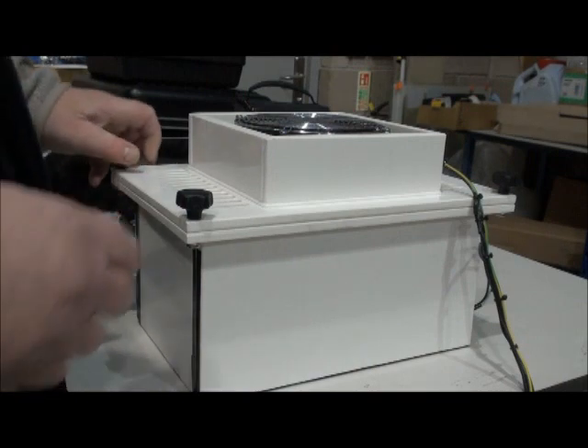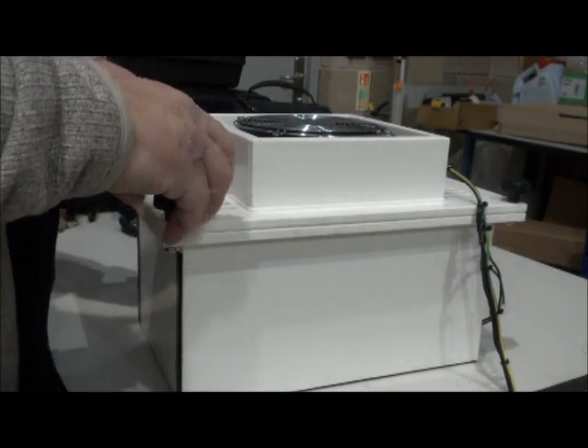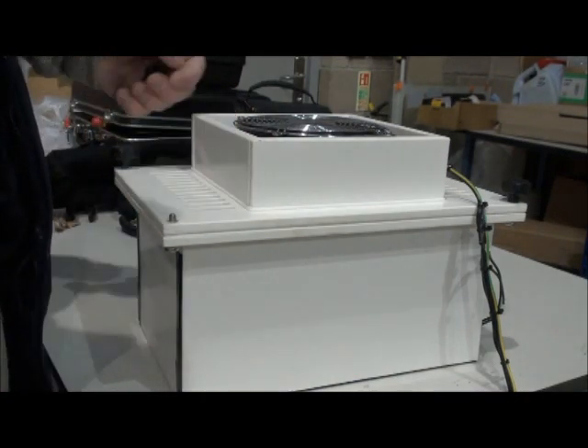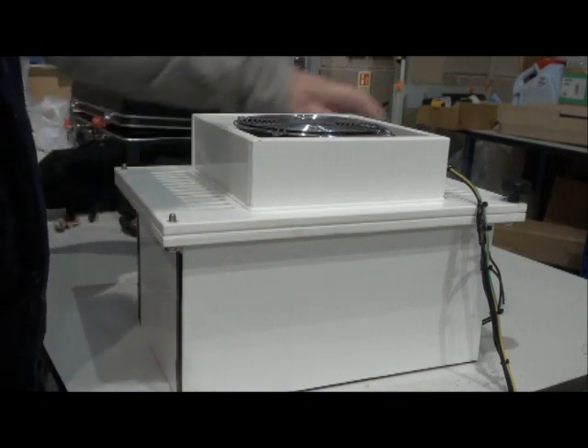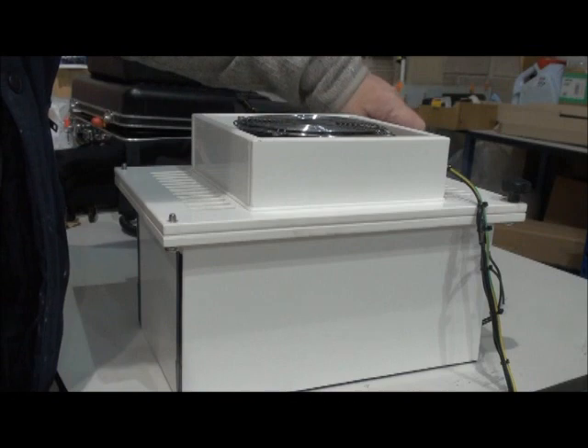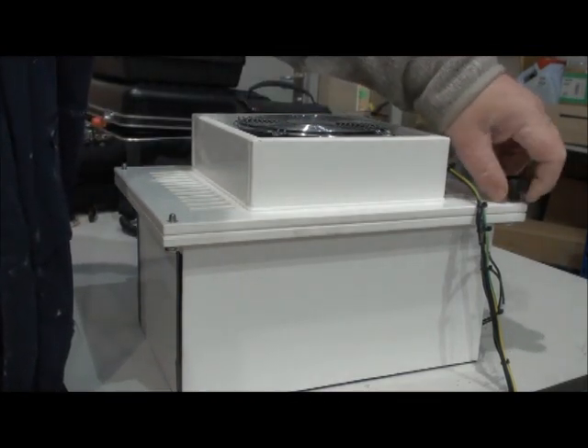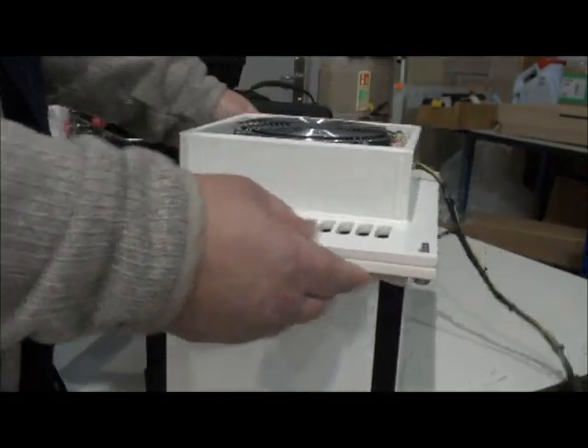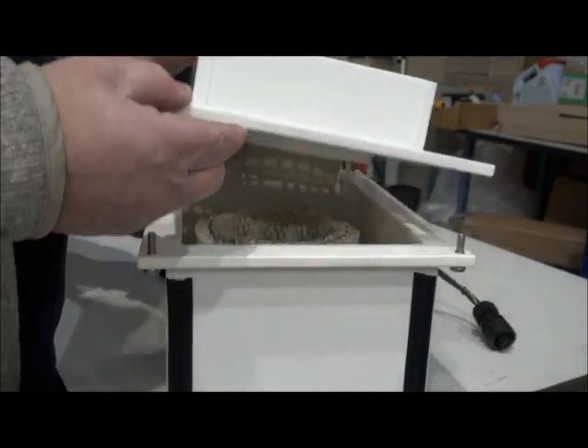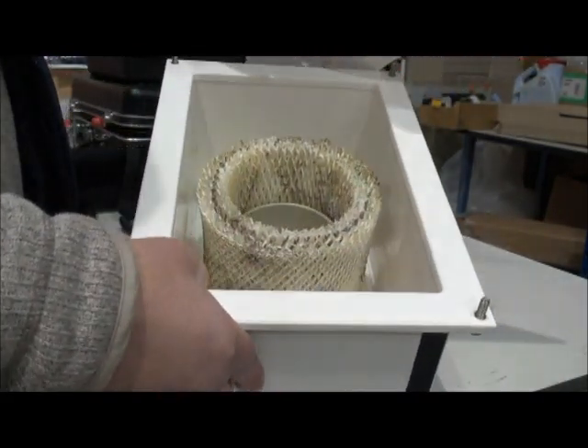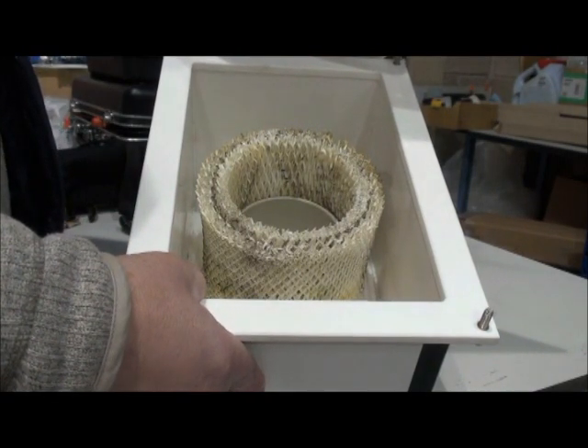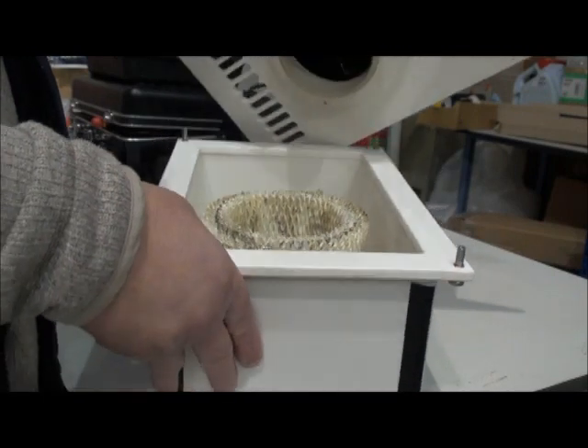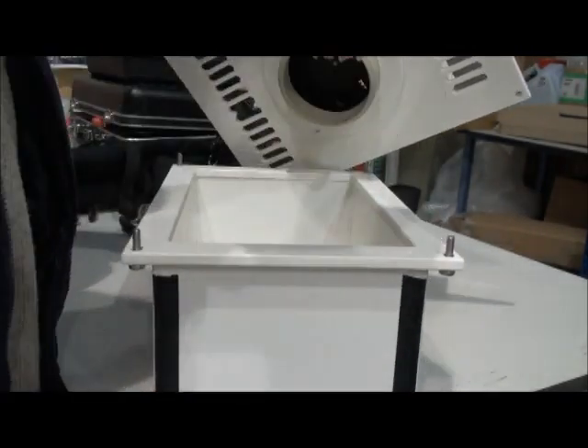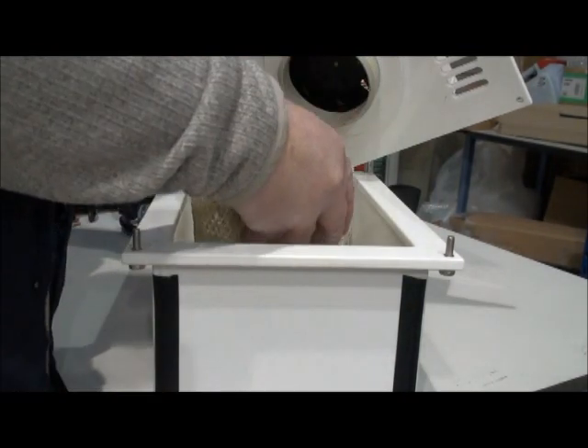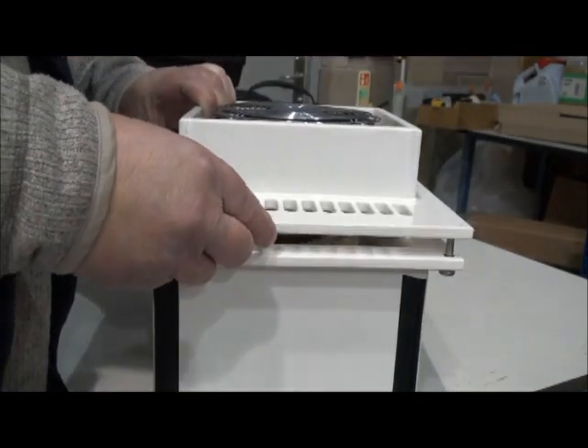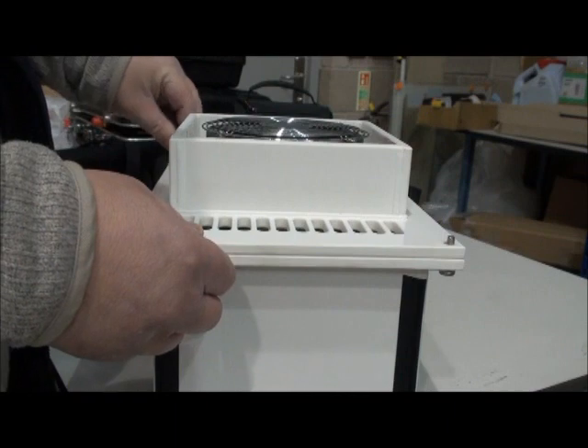Here we can examine the humidifier. To access the humidity filter, you remove the nuts on the top of the humidifier box. Remove the lid, and this will expose the wick filter located inside of the chamber. Remove the wick filter, and replace with a new one over the spigot, on with the top, and resecure.